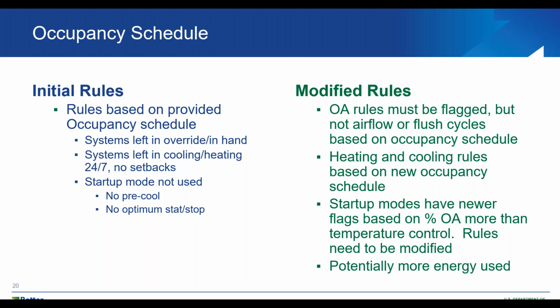So again, the rules. I've stated some of them, but just to sum up, you have initial rules based on startup, systems left in override or not running according to the occupied schedule initially. And then you'll have modified rules. So what happens with new heating and cooling rules? Maybe the heating and cooling is not used anymore. They're letting it run 24/7, but they don't let the heating and cooling run that time. You need to modify the existing rules to indicate what the current schedule's like.